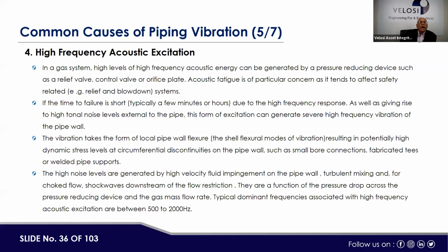Then there is high frequency acoustic excitation. For example, in a gas system, a high level of high frequency acoustic energy can be generated by pressure reducing devices. For example, if you have a PSV and the PSV is lifted and very high flow goes to the flare side, it can cause vibration. There are control valves and pressure reducing valves, and in those areas also there could be high energy, where pressure is converted into velocity, and velocity is high in the low pressure zone. In that scenario, there could be high frequency vibration and sound as well.